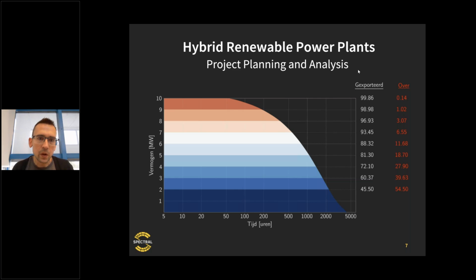So in fact, the answer was 0.14%. What you see on the graph is analysis based on the plant in question. On the x-axis, which is a logarithmic scale, you can see there are only about 60 hours per year where production goes above the 10 megawatts rating of the grid capacity.